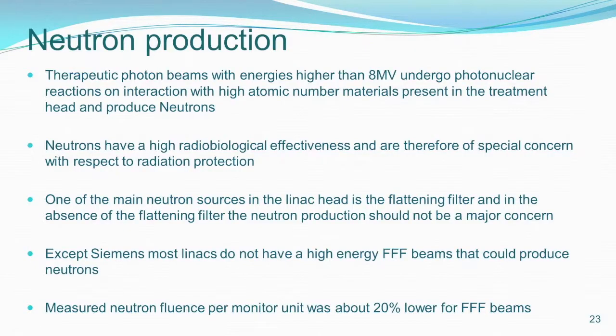The other thing is the neutron. Therapeutic beams, as I said earlier, with energies greater than 8 MeV undergo photonuclear reactions when they interact with high atomic number material, and they produce neutrons. Particularly, it happens in the treatment head when they interact with the various collimators and other things. And the neutrons have high radiobiological effectiveness, and therefore it is of concern in radiation protection. One of the main sources of neutrons is the LINAC head, and the flattening filter in the LINAC head. Now, if you remove that, then there is a significant reduction in neutron production. So it is not really a major concern.